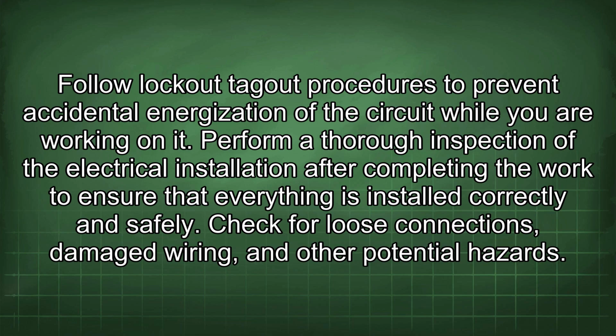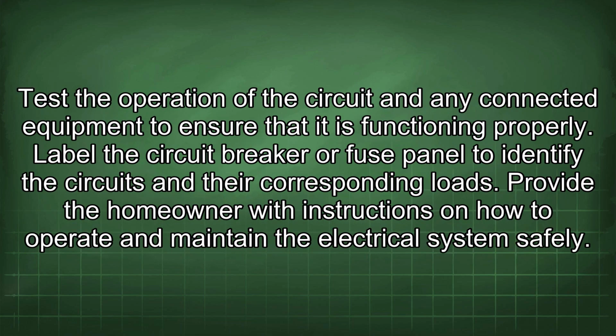Perform a thorough inspection of the electrical installation after completing the work to ensure that everything is installed correctly and safely. Check for loose connections, damaged wiring, and other potential hazards. Test the operation of the circuit and any connected equipment to ensure that it is functioning properly. Label the circuit breaker or fuse panel to identify the circuits and their corresponding loads. Provide the homeowner with instructions on how to operate and maintain the electrical system safely.